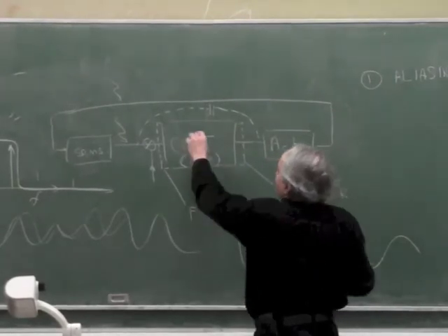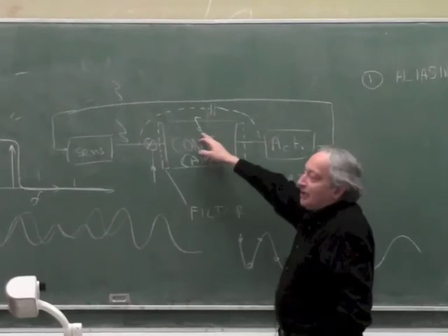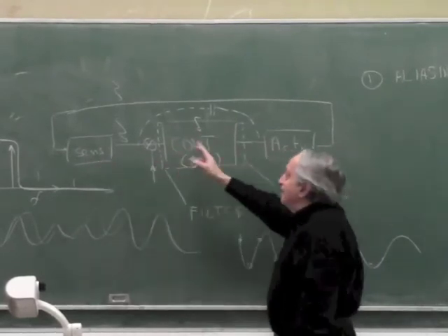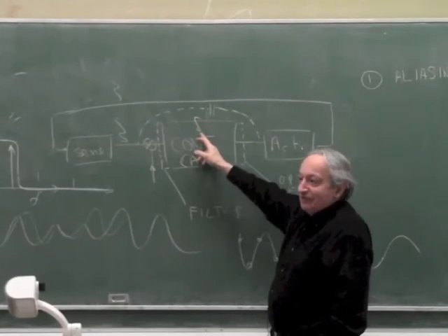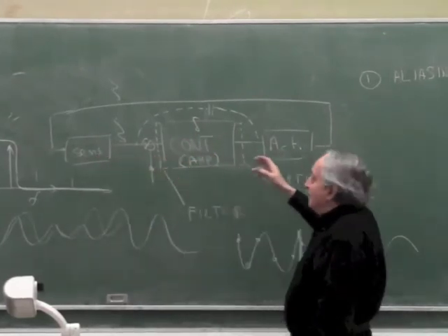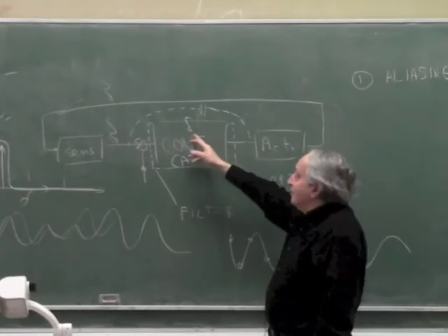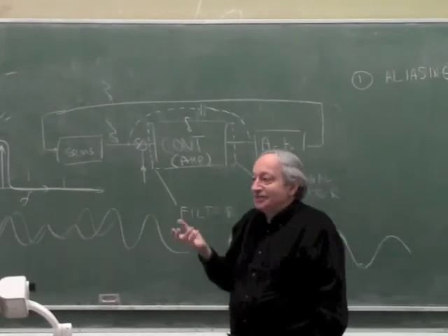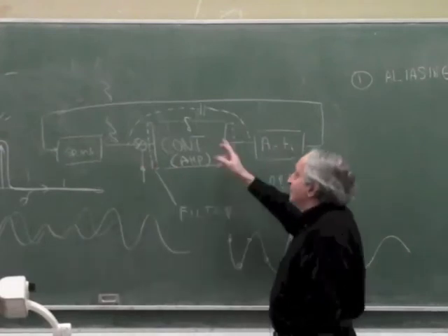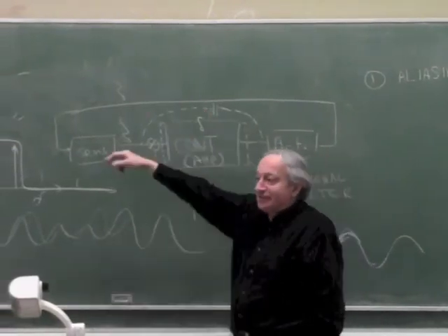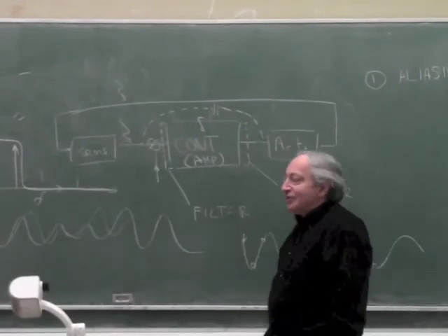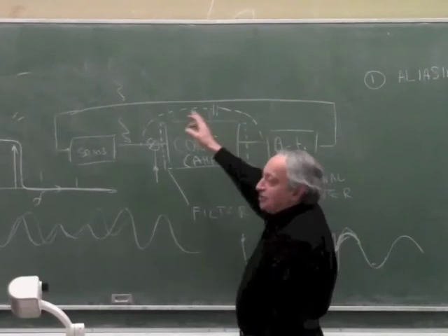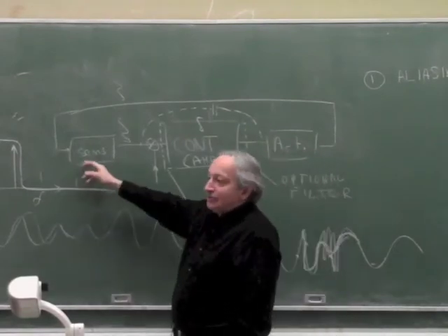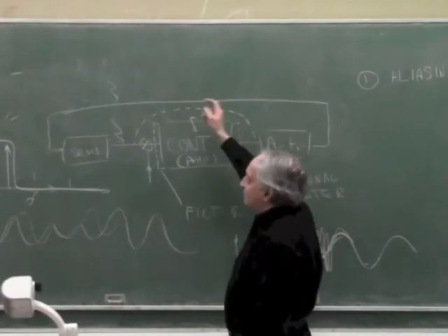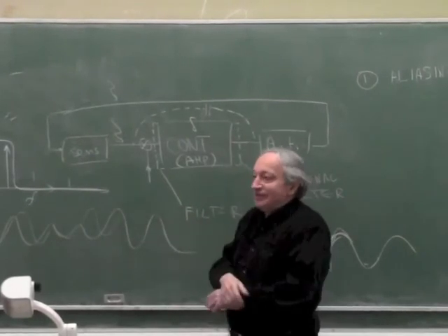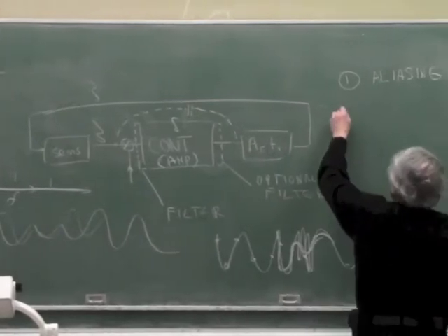Every system has a delay, delta. Say this delay is a microsecond—at our normal operating frequency, this delay doesn't cause much phase shift. But if a 2 megahertz signal, or even a 1 megahertz signal gets in, 1 microsecond corresponds to 360 degrees. So even a half megahertz signal getting in with a microsecond delay causes a full phase reversal. If we don't limit high frequencies, we can get oscillations in the system—not at the frequency we're trying to control, but at the high frequency, which finds it much easier to shift phase and feed back.